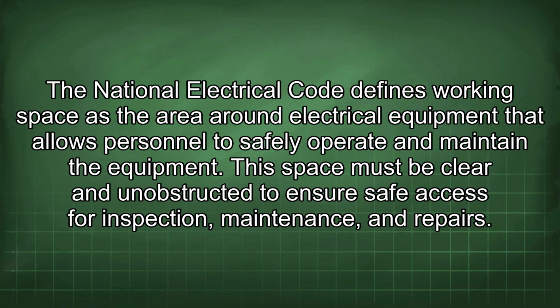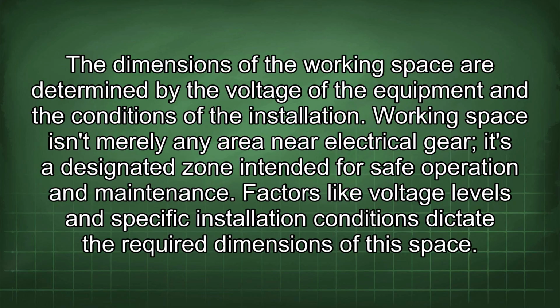The National Electrical Code defines working space as the area around electrical equipment that allows personnel to safely operate and maintain the equipment. This space must be clear and unobstructed to ensure safe access for inspection, maintenance, and repairs. The dimensions of the working space are determined by the voltage of the equipment and the conditions of the installation. Working space isn't merely any area near electrical gear, it's a designated zone intended for safe operation and maintenance. Factors like voltage levels and specific installation conditions dictate the required dimensions of this space.